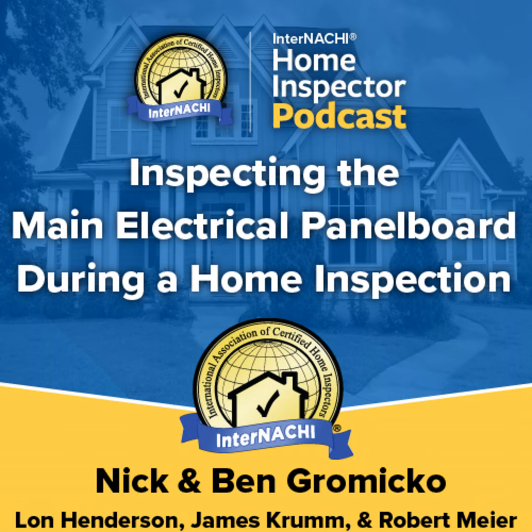Safety issues with panel boards, such as Federal Pacific Electric. There's a general consensus among electricians and many industry experts that some electrical panels have significant safety issues. Federal Pacific Electric, or FPE, Stab-Lok panels, Zinsco, GTE Sylvania, Bulldog Pushmatic, and Challenger distribution panel boards are the most commonly encountered among these problematic panels. The recommendation for these panels is to replace the electrical panel board. There are no recalls on these panel boards, with the exception of approximately 1,000 Eaton Cutler-Hammer panels in 2014 that were built on the Challenger design.